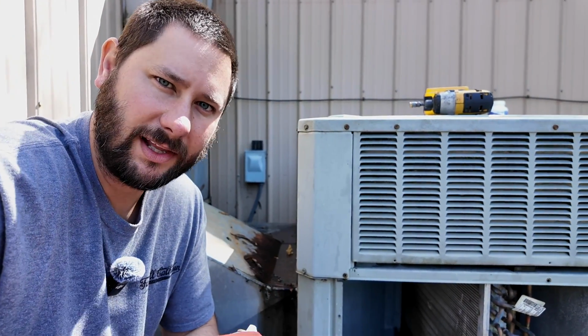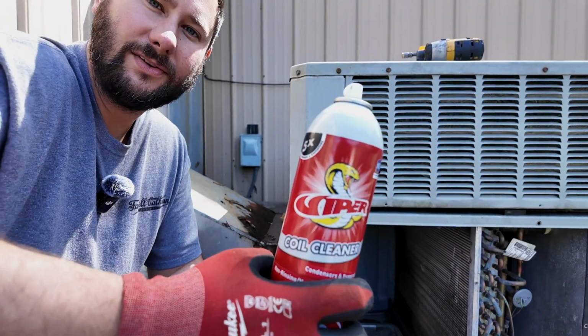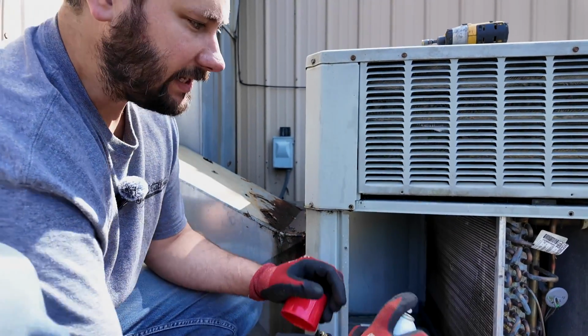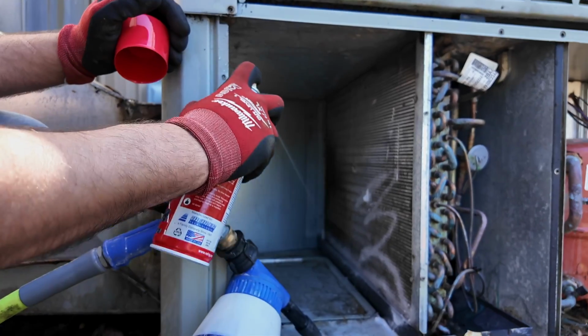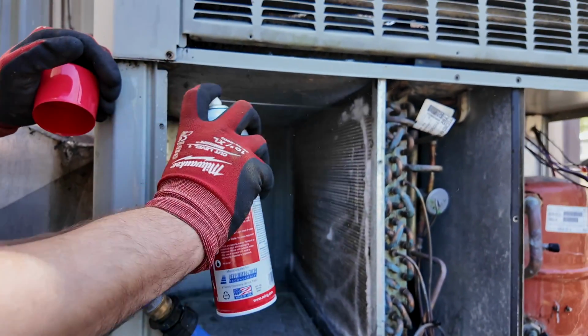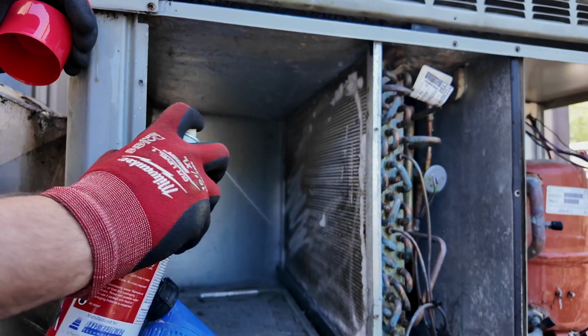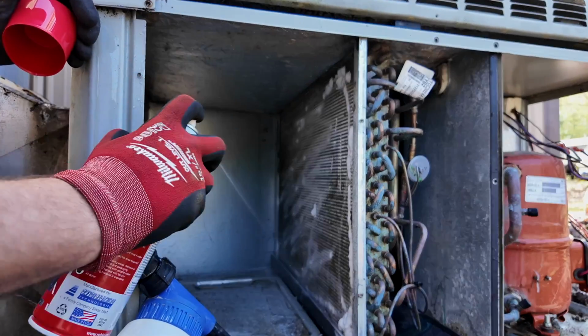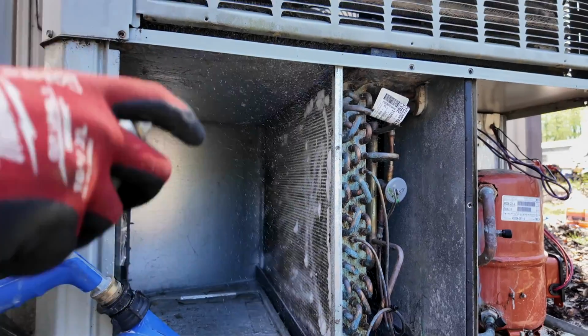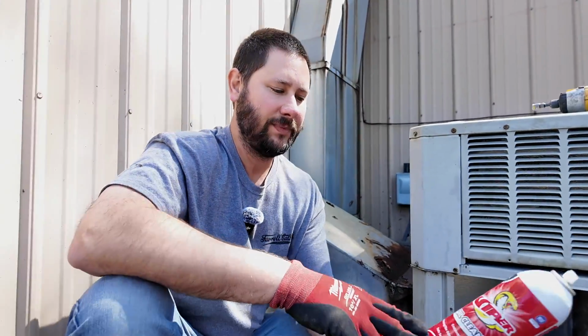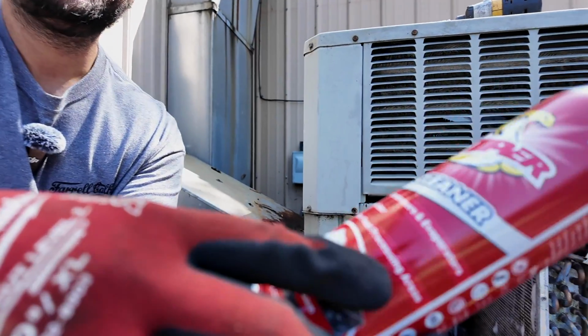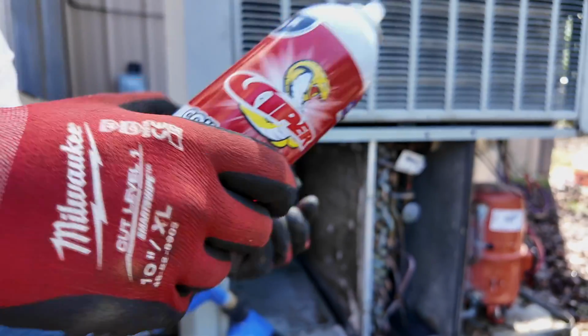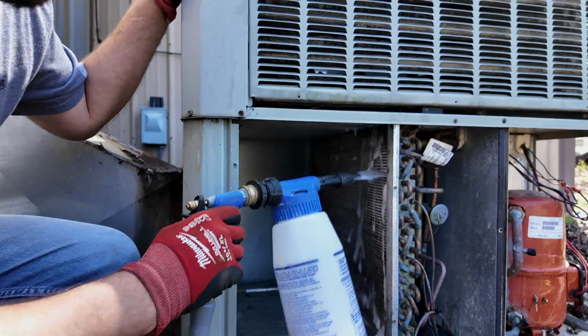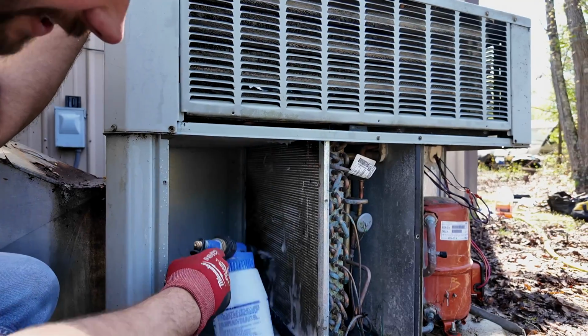Now, to make sure that we have the best indoor air quality, we gotta make sure we clean the indoor coil. And this is where I may use some of the Viper coil cleaner, especially if it is a split unit. And I'll show you a split unit and an indoor coil. This right here, you just spray it on like this. And some of these coil cleaners, like the ones in the cans, are self-rinsing. So this right here is no rinsing, non-rinsing, no odor. I don't want to use this because I believe this is much stronger. So I'm going to use this coil cleaner. We're going to make sure we douse this coil.